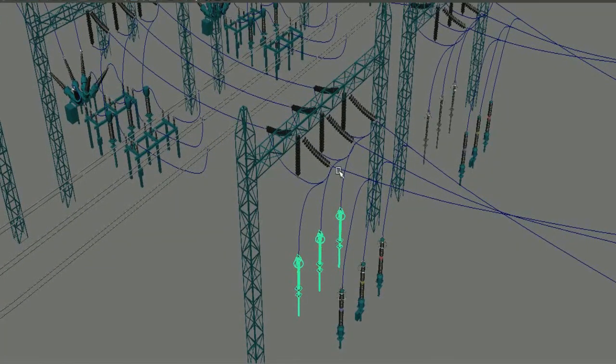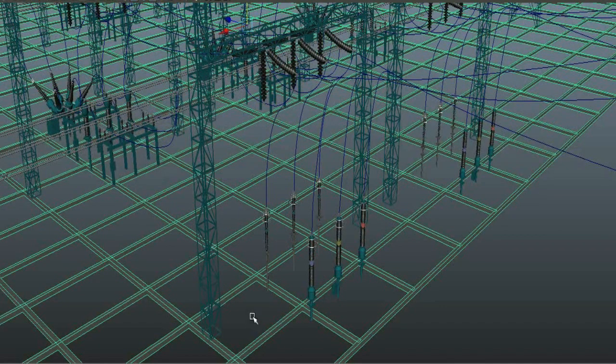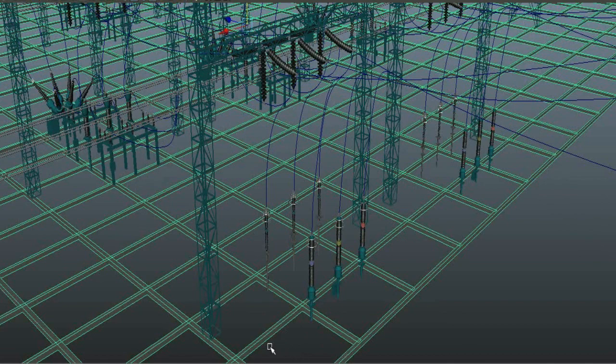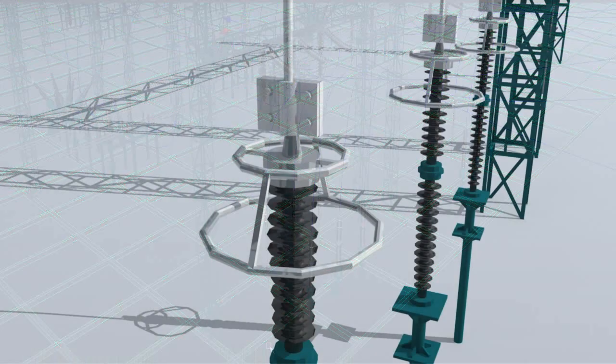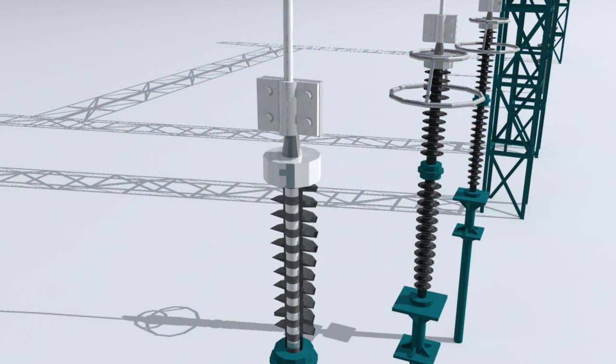Here, the meaning of parallel connection is that one end of the arrestor is connected to the line conductor and the other end is connected to the metallic earth grid beneath the substation ground. Such arrestors are made up of material which possesses high electrical resistance for normal voltages.